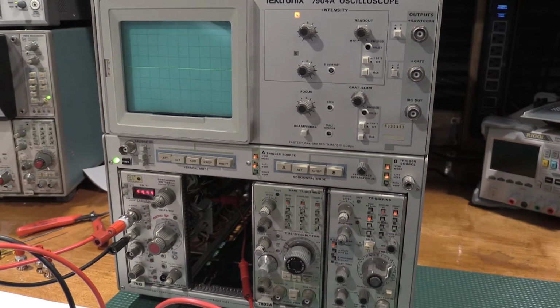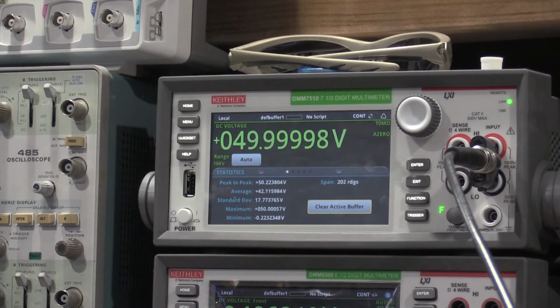Nope, I mistakenly used the calibration generator, and I have some of the settings wrong. The calibration generator needs to be a DC calibration generator. So in my case, I'm going to use the Fluke. What is this thing? The 343A, because that'll give me the precision I need. I need to set that to 50 volts, so I'm going to do that now. Okay, so we have 50 volts as precisely as I can generate it in my lab.